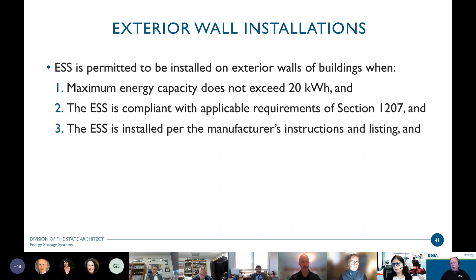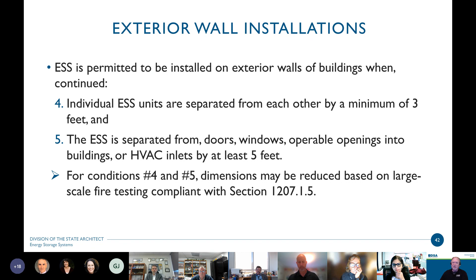When we mount these on the exterior of a building, they have to be separated from each other by a minimum of 3 feet. And they have to be separated by 5 feet from any doors, windows, or operable openings or HVAC inlets on the building. So for these two right here, 4 and 5, it's noted that these can be reduced based on large-scale fire testing. So we're not limiting you. We're not saying you can't do it. We're just saying if you want to go less than the separation requirements here, we're going to need some listing documentation that this wall-mounted unit has been subjected to the 9540A testing requirements.